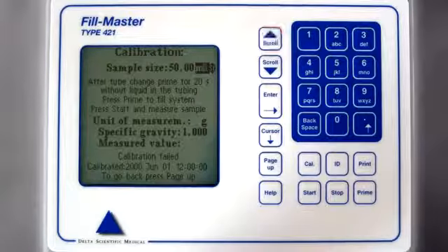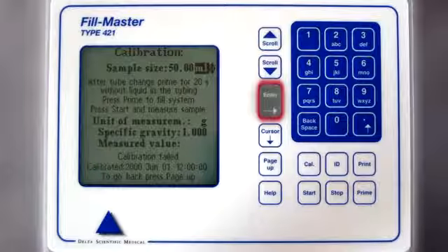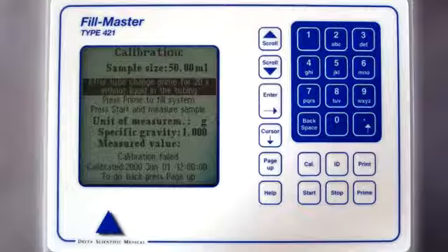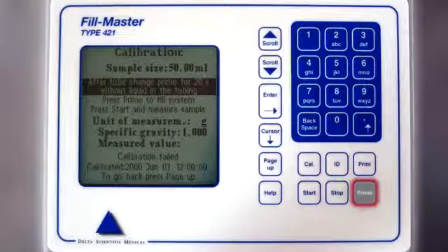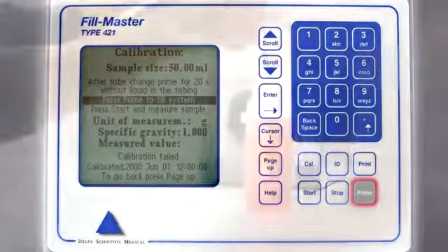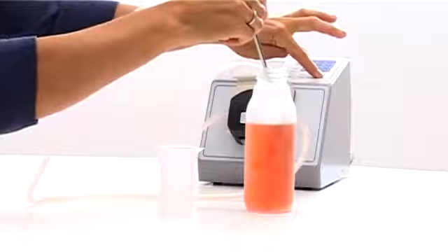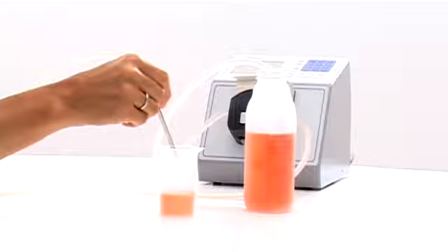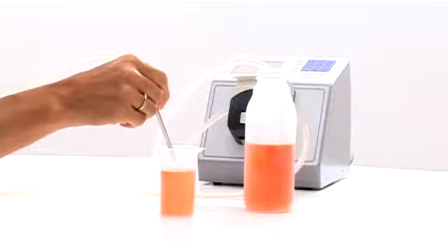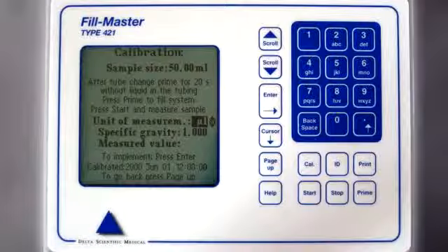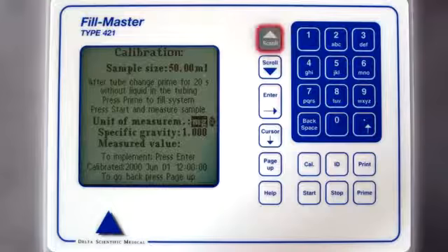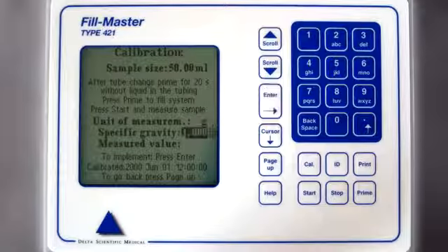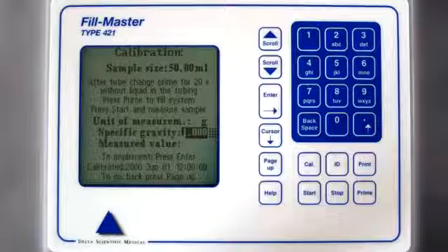Now use the scroll buttons to choose between microliters and milliliters and press Enter. The cursor is now in a line which encourages you to prime for 20 seconds in order to take the basic stiffness out of the tubing applied. After that, use the prime button to fill the system. Then press Start to obtain your sample and measure it. The cursor is now in the field Unit of Measurement. If you use a measuring cylinder, use the scroll buttons to go to microliters or milliliters and press Enter. If you used a balance, use the scroll buttons to choose grams or milligrams.